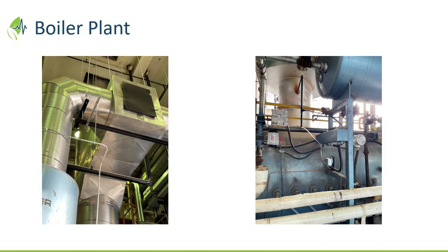Otherwise, you start to dump the heat where you don't want it. And flow is critically important in any boiler, any heat exchanger for that matter. If you don't have sufficient flow at all times, you will fail. Is there a software sensor that alerts you? Yep, these boilers come standard, as most do, with indicators on the heat exchangers themselves as well as stack temperature.